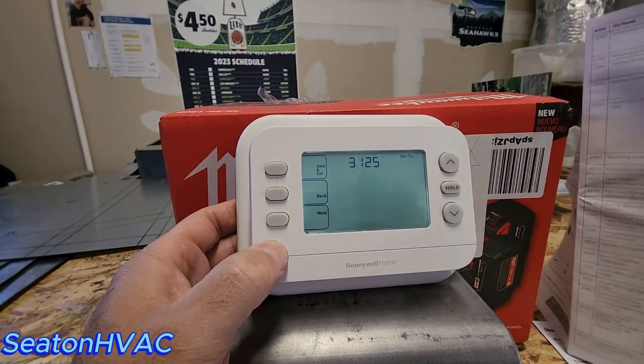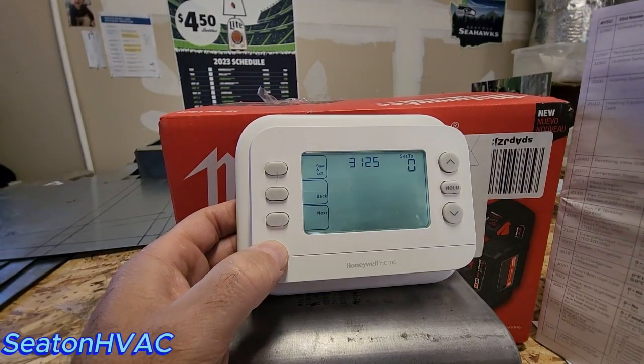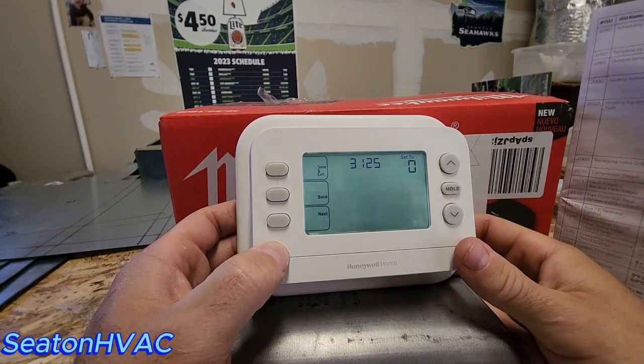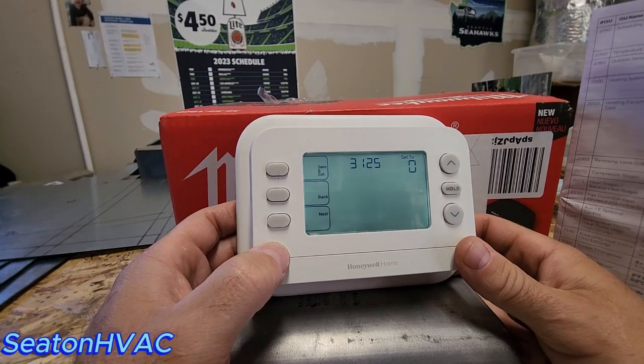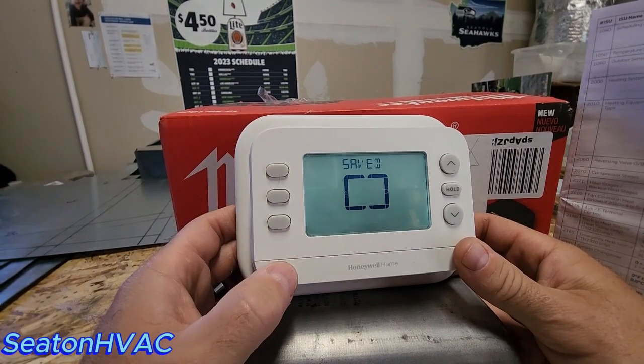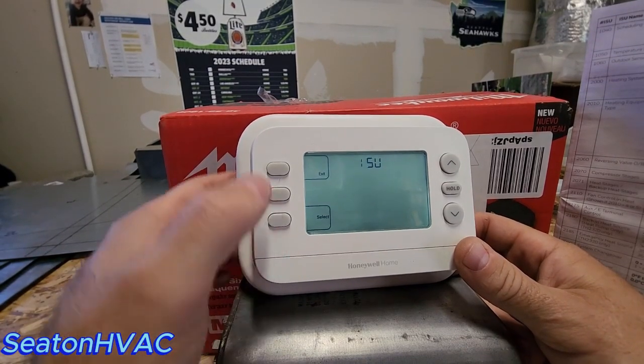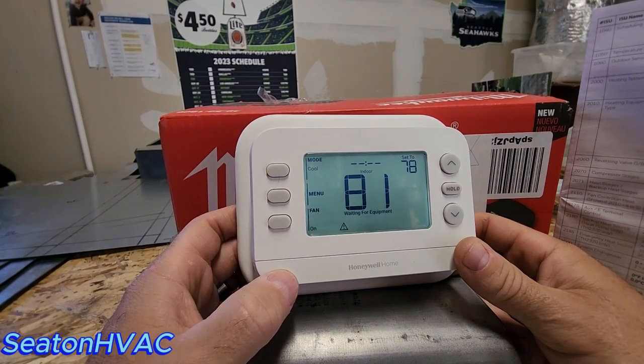And then it goes to 3125, which is lockout fan after a cool call. Some people don't like the fan to still run. Just turn it off, and then the fan shuts off with the cooling. And that's pretty much it. Then you'll hit save and exit. Exit again, and then all your settings are locked in there.